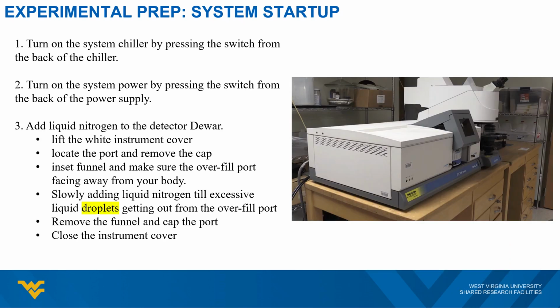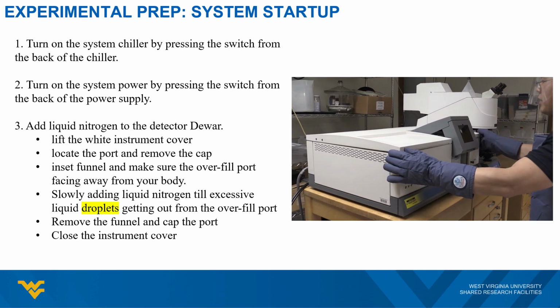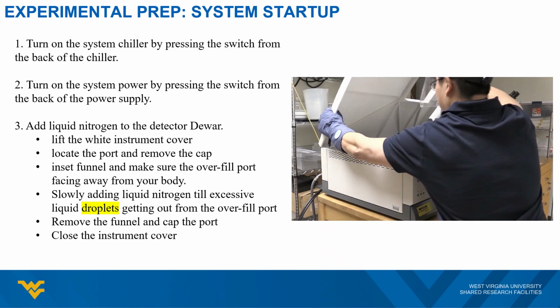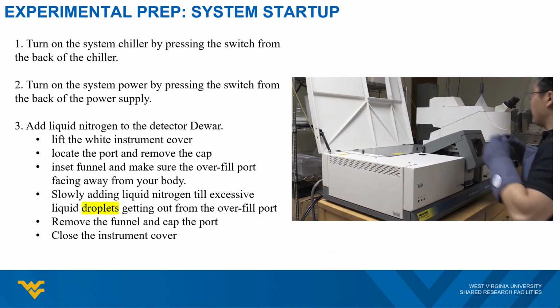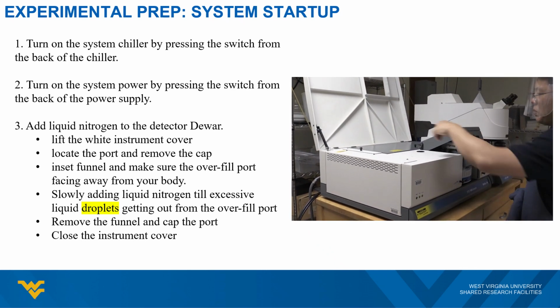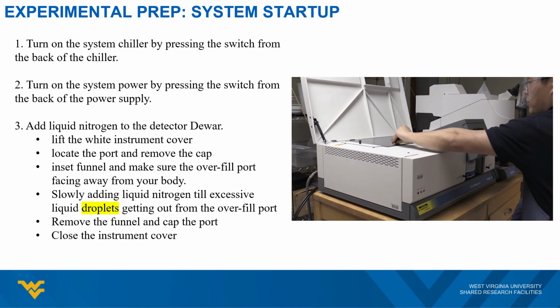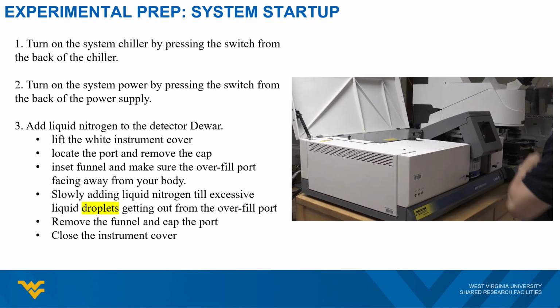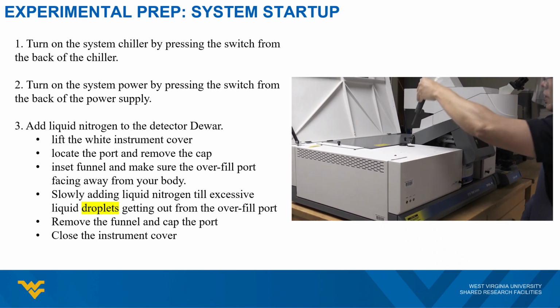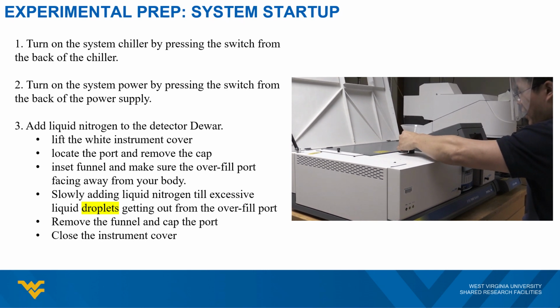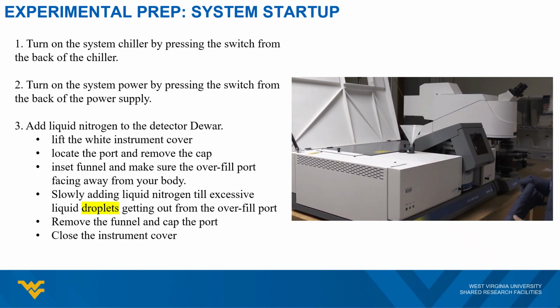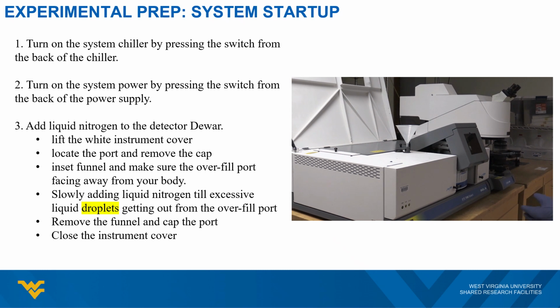Now we are ready to add liquid nitrogen to the detector dewar. Begin by lifting the white instrument cover, spot the port, and remove its cap. You will want to insert a funnel into this port, taking care to ensure that the overfill port is directed away from you.